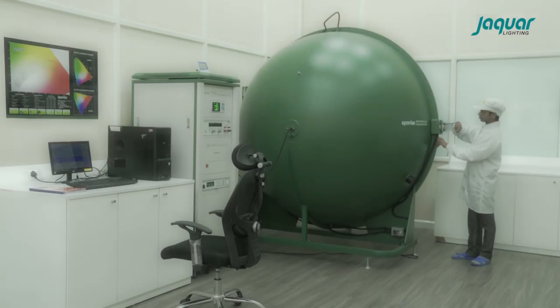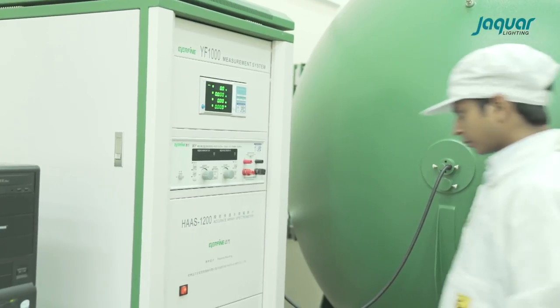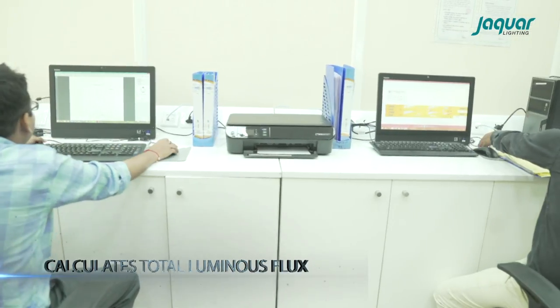Optical testing includes a photometric integrating sphere that is equipped for self-absorption measurement and correction, and a gonio photometer that measures the luminous intensity of the light source at different directions and calculates the total luminous flux.